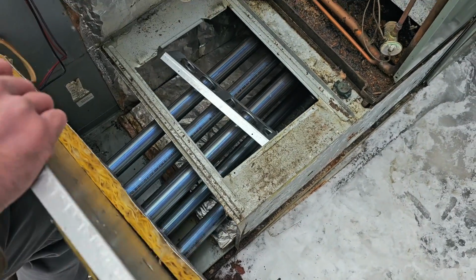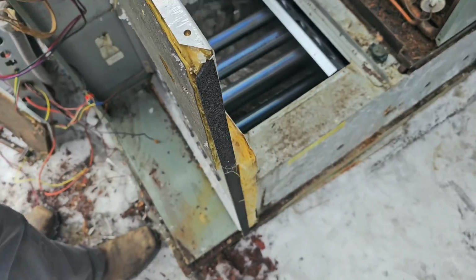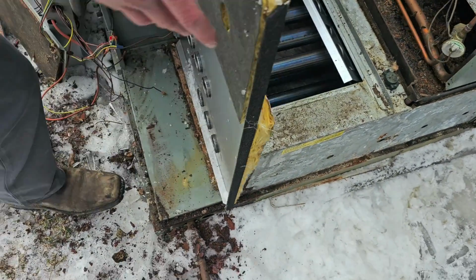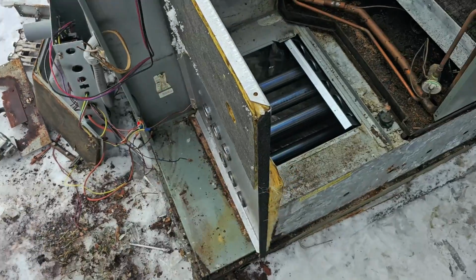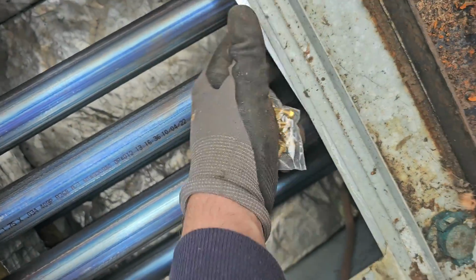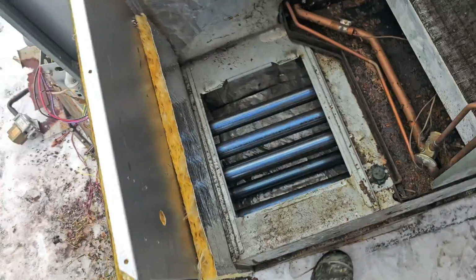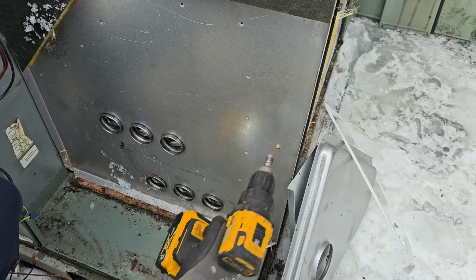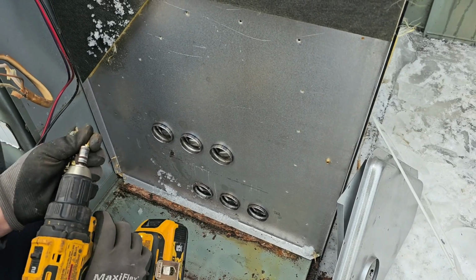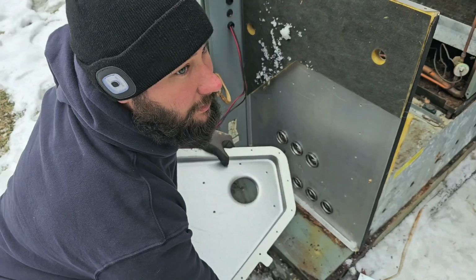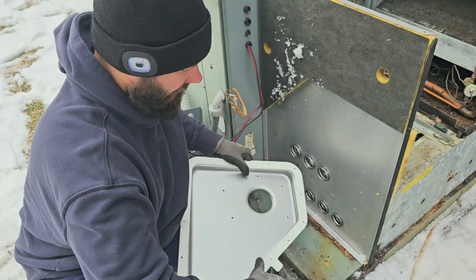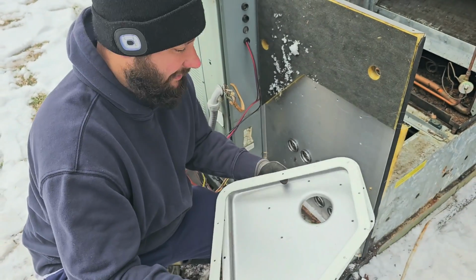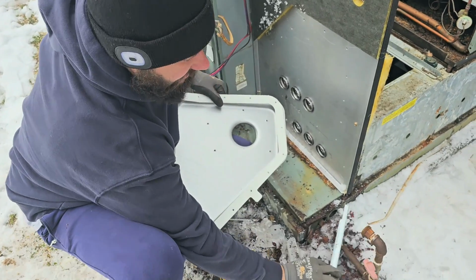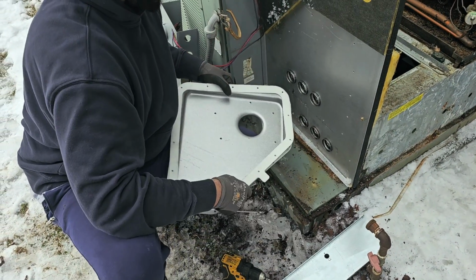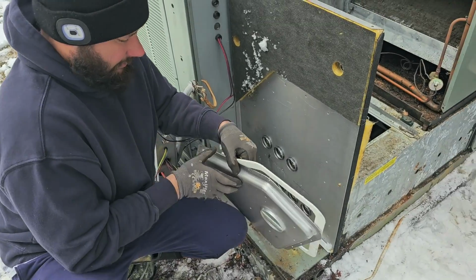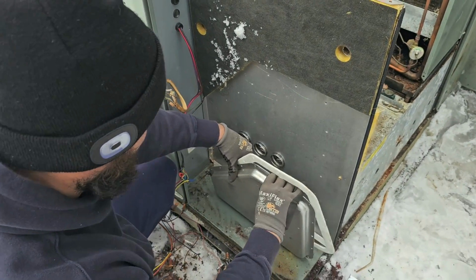Like a glove. Slide it up, and then we'll start with those 2 1/4 inch screws, and then I'll put the flue box cover on. And this is lined up right here. If it lines up, nice. We got a new gasket for our inducer motor assembly. We got a new gasket for our flue box cover. Definitely use the gaskets. Also, we've got this little plate right here where the rollout switch mounts to, because it was rusted. It was pretty much looking like a piece of metal.